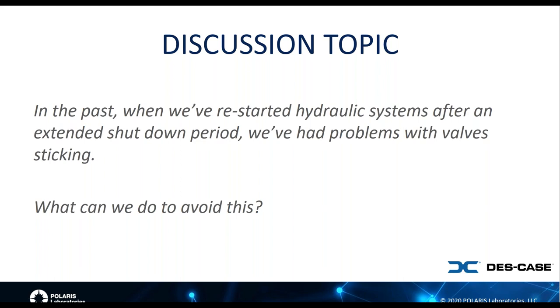Where the problem lies is when the oil shuts down and cools down, and as that temperature drops, the soluble byproducts of oxidation start to come out of solution. And when they do that, again, they're very sticky, very resinous. They get trapped on the inside of the spool and the bore of a valve, as an example.